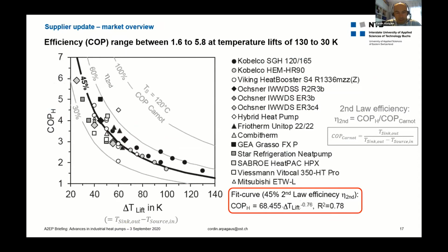Now about the efficiency. You know, the COP, as I showed before, is the useful heat divided by the electrical power consumption. And typically we have a COP of 4. So it means 1 part electricity gives 4 parts useful heat. And this is at a temperature lift of about 40 to 50 Kelvin. The temperature lift is the temperature difference between the heat source and the heat sink. So we have waste heat, for example, as a heat source at 40 degrees. And then we have a 50 Kelvin lift, which gives a 90 degree heat sink. So a COP of 4 or 3 can be expected.